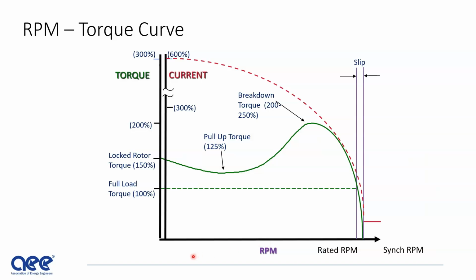In terms of RPM versus torque, here you see torque on the y-axis and RPM on the x, and you can see what the natural curve is to this red dotted line. In actuality, what happens is there's a breakdown torque, and then there's a pull-up torque, and then a locked rotor torque. So this is a classic torque curve. Different classes of motors have different torque curves, and we'll get into that very briefly here.